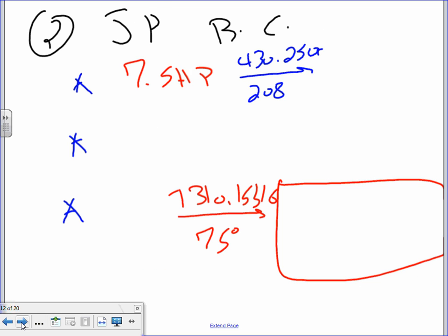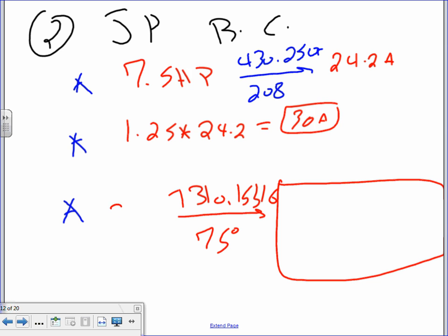All right, so let's go find 2. 2 is very easy, 7.5. At 7.5, guys, the full load is 24.2 amps. Same thing, 1.25 times 24.2. That'll get you a healthy 30 amps. And then you take the 30 amps, that's easy. 30 amps, take it to 310.15(B)(16), and that will get you 3 conductors, number 10 AWG, RHW. If I ask you to size the conduit, would you be able to size the conduit? Yes. No problem. Any comments, guys? Any questions about the branch circuits? Branch circuits, Derek, are straightforward, no gimmicks, nothing. Straightforward.